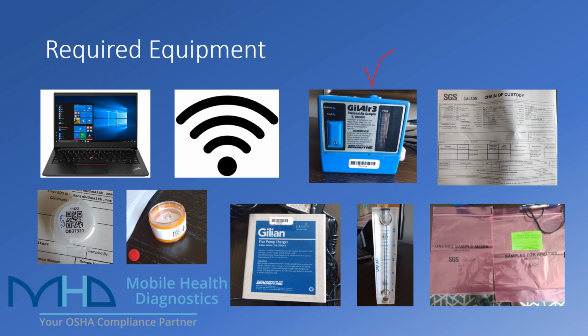This little guy sitting right there, that's an air pump. That is what's going to be pumping air through the tubing that is situated on any of the collection media devices. So you're going to get to know those. This little hatch right here we'll talk about later, but that is a cover that covers the power switch and the calibration screw. There's a screwdriver that's going to be provided in the kit, so keep in mind that if you can't find the power switch, it's probably under that cover.